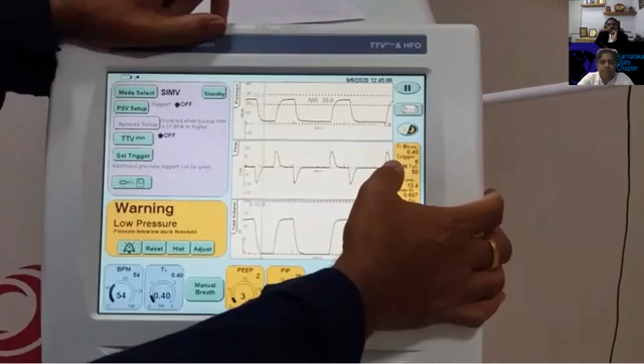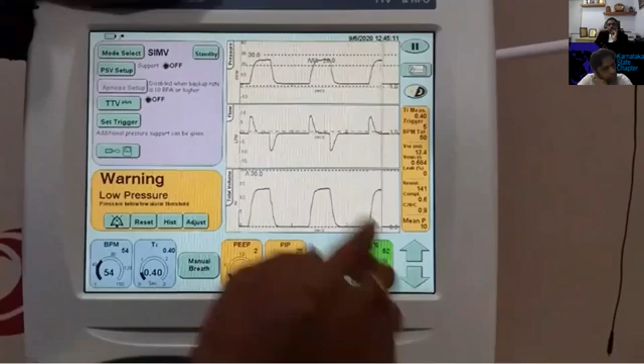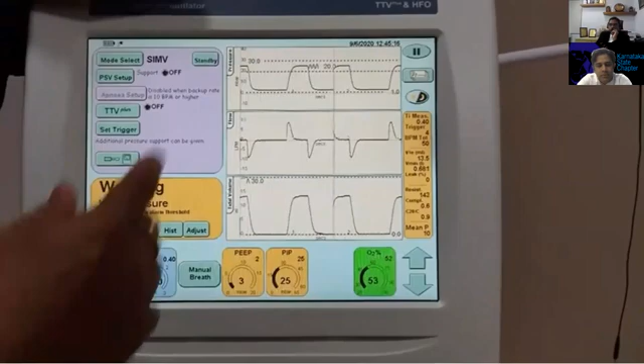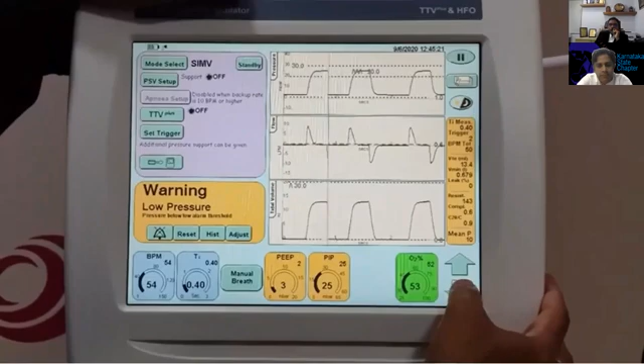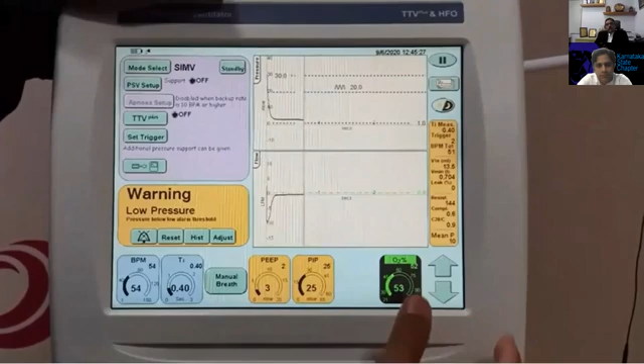What you're seeing in brown is the level where the triggering is, and it is around 0.6. Generally, if you keep it at around 1 or above, the triggering will not happen and you will not see the baby triggering the breath. So ideally, you should keep it at around 0.4 to 0.6, where the trigger sensitivity will be very high.